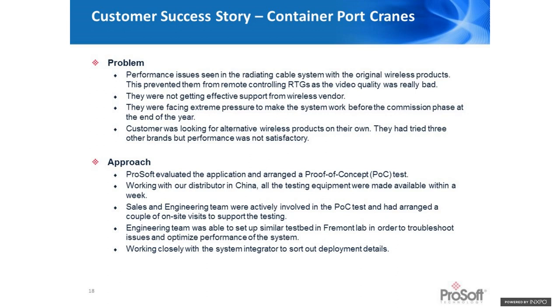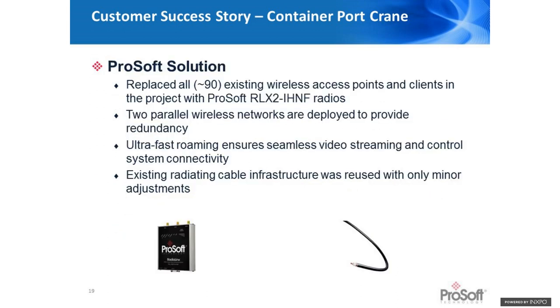As a result, they deployed the ProSoft radios across the entire port. It was over 90 radios, 30 on the cranes, and another 60 access points. And they're using 2 parallel networks for redundancy, which makes it even more reliable.